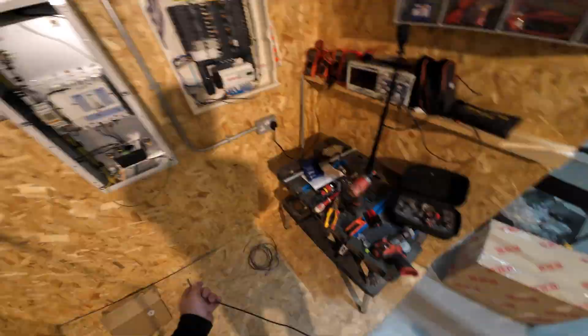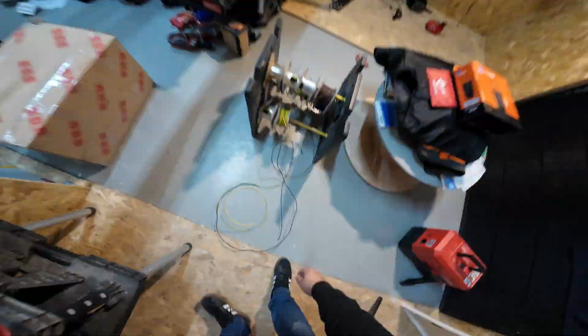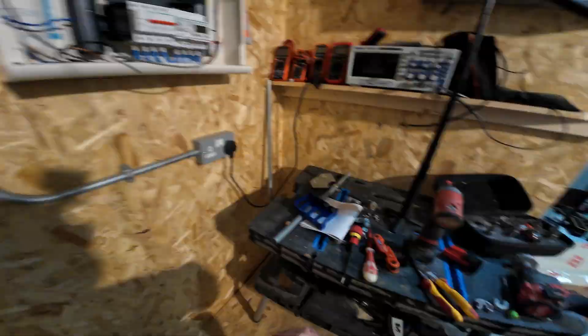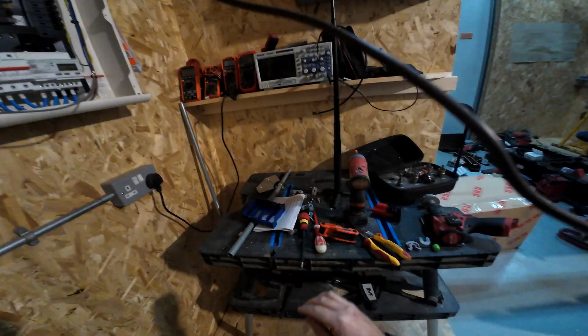This is just my methodology with not having black and grey cable, and yeah, it's a training environment, so go easy in the comments. Obviously these are only 4mm conductors, so they're massively undersized for the purpose, but there is a C16 in advance of all of this down at the main panel board, so we are suitably protected anyway. In the real world you'd have much bigger conductors, and you'd need bigger openings in your containment, possibly bigger containment itself. So it can look a little out of place because of those smaller cables, but we're just getting them in there. It's just to show the features of this product in a training simulated environment rather than real world applications.